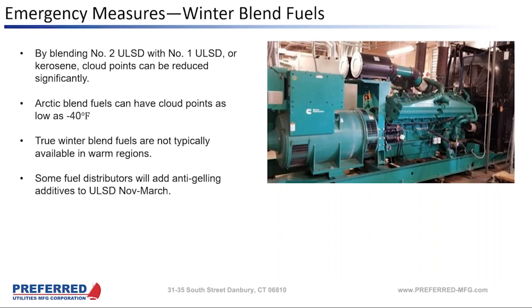They're in the process of expanding McMurdo Station in Antarctica, and we're doing the fuel system there. When the inquiries first came in, I saw McMurdo Station, Antarctica, but no heaters. They specified fuel polishers, transfer pumps, day tanks, but no heaters in the system at all. So I got past the purchasing person and got to an engineer working on the system, and they said, no, we're good. They burn an Arctic blend down there that has a cloud point of minus 40 F, and even in Antarctica, they're able to keep the oil above minus 40 F without heaters.